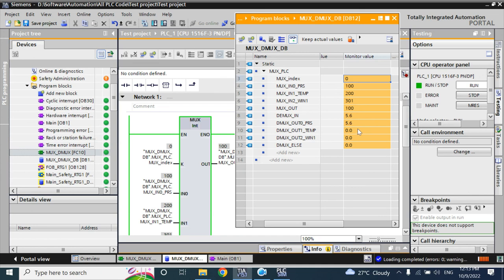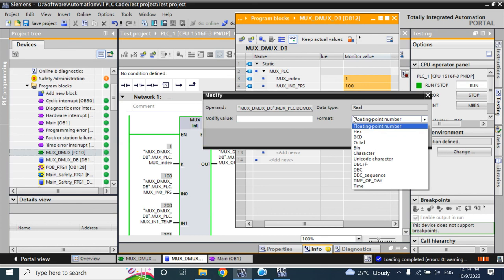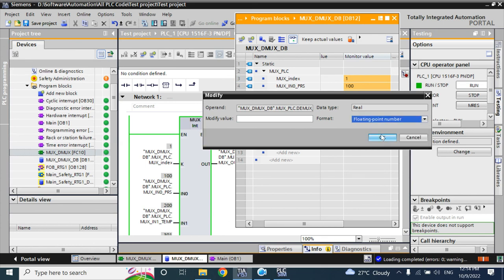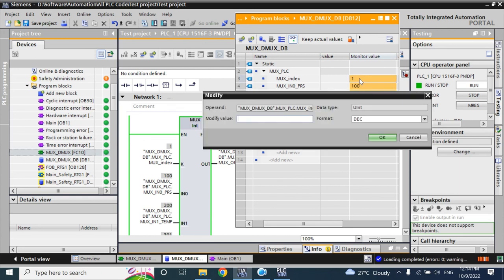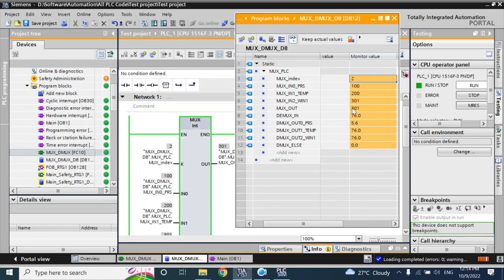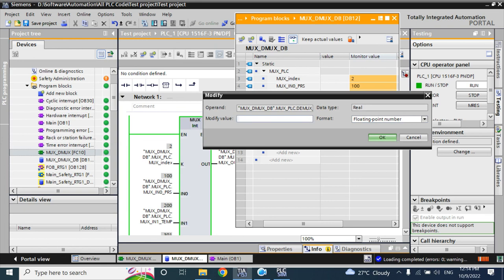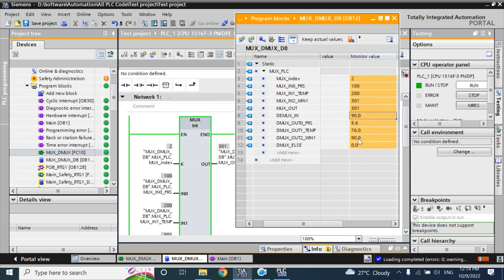Now if you set the index to 1, it requests the controller for outlet temperature. Think that the outlet temperature is 75 or 76 — it is now going to outlet temperature: 76. Now if the index value is 2, it requests for 301 — winding 1 temperature. If the DEMUX input is now 90 as winding temperature, it is now going to winding temperature: 90.